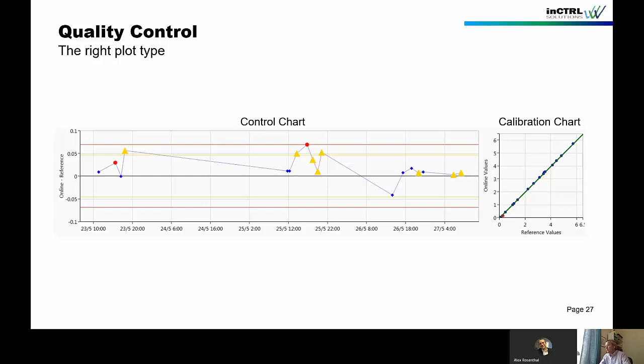The first question really to ask is, when do you collect the sample, right? So that means next to the probe. Don't do that every morning at 8, right? Because then you will just have a little tiny cloud of data. What you want is to cover most of your measuring range. If you cannot do that because the working range is too small, you have to design special experiments. For example, a bucket test where you spike high concentrated standard, right? Very important design for that.